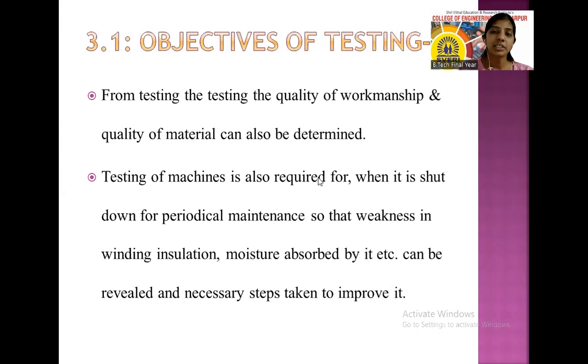Sometimes testing is also necessary when there is a shutdown for periodical maintenance. Sometimes machines may be shut down for some duration, so after that you have to check the performance of the machine. The periodical maintenance may be annual, weekly, or monthly. During that maintenance period you also have to check the weakness of the winding insulation, whether moisture has been absorbed by it or not, etc. That can be found by testing. What are the deficiencies in the performance of the machine should be checked, and necessary steps can be taken to improve the performance of the machine.